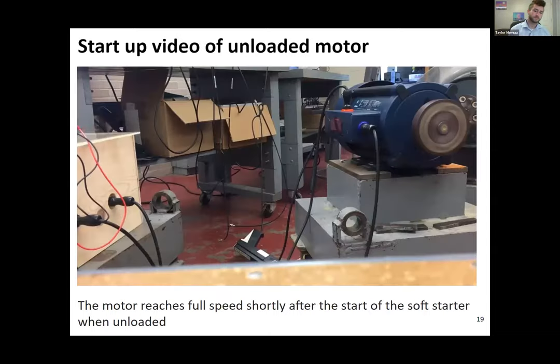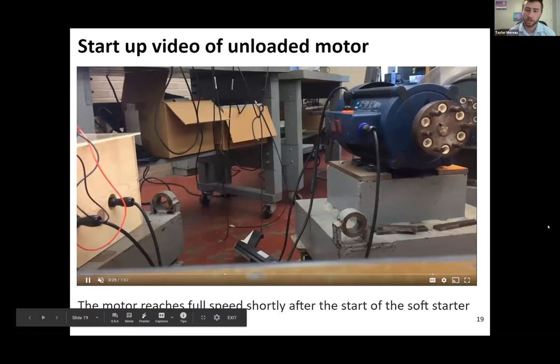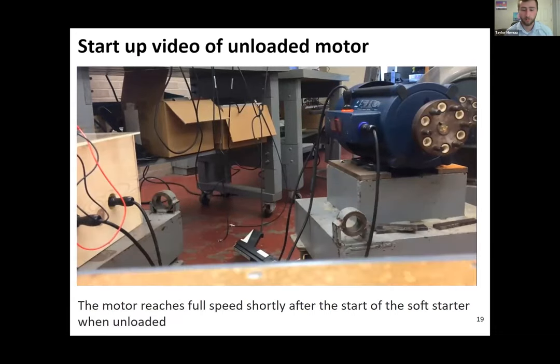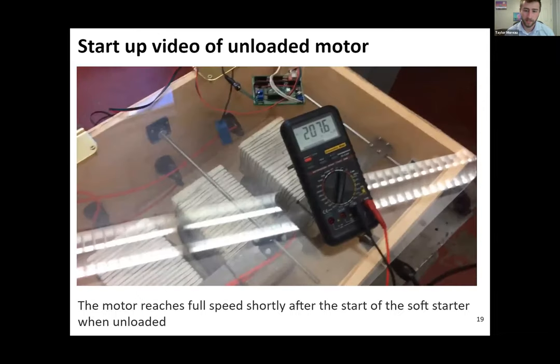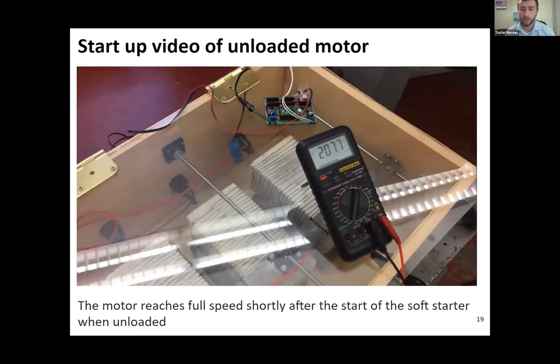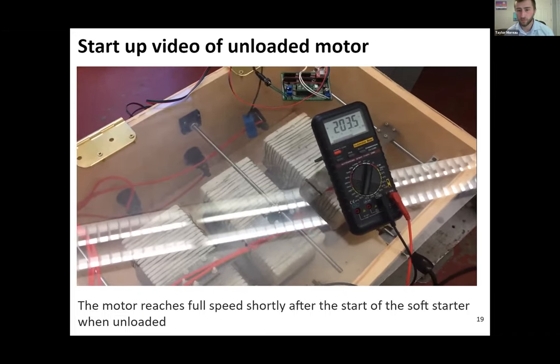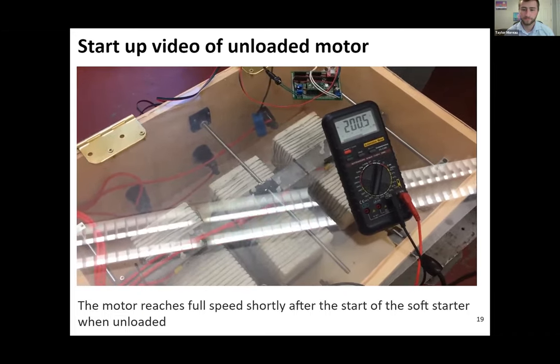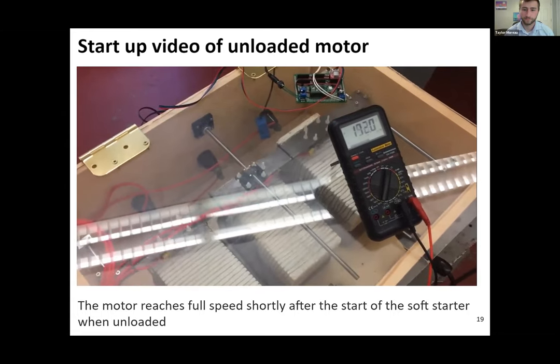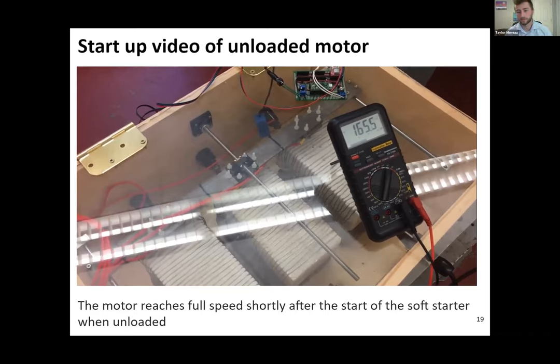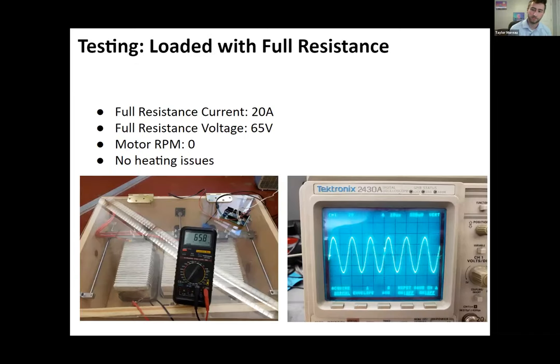Next slide. So this video shows the unloaded motor starting up with the soft starter in operation. The RPM does reach its 3,600 RPM almost instantaneously. So there was no delay compared to with the motor hooked straight to power. And this is showing the voltage of the motor at no resistance and moving back. Next slide. I'll turn it over to Jeremy again for more testing data.